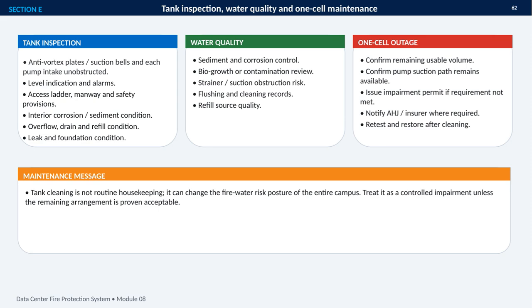That is why flushing and cleaning records matter, as does confirming the quality of the refill source. For a one-cell outage, we must confirm the remaining usable volume and make sure the pump suction path is still available. If the required arrangement cannot be demonstrated, an impairment permit is needed, with notification to the authority having jurisdiction or the insurer where required. After cleaning, retest the system and formally restore it.